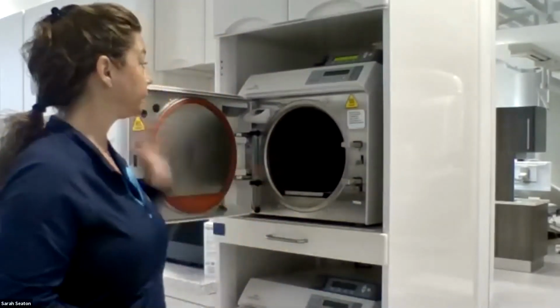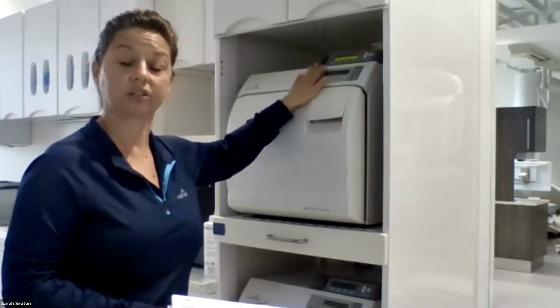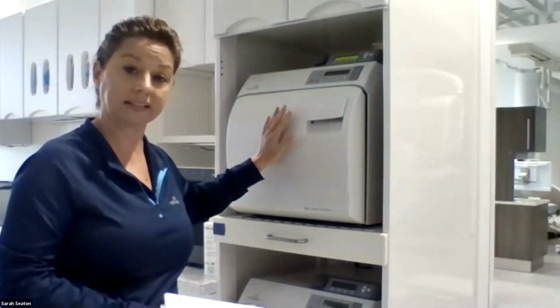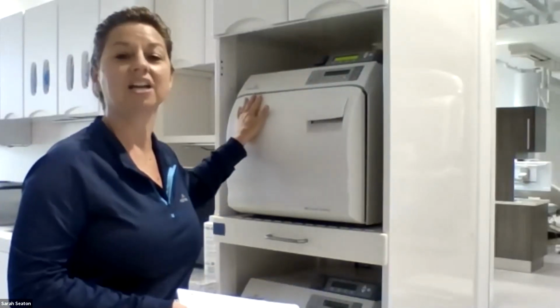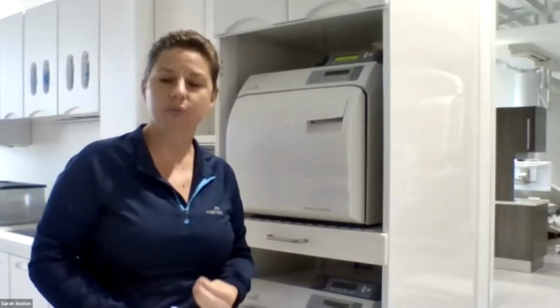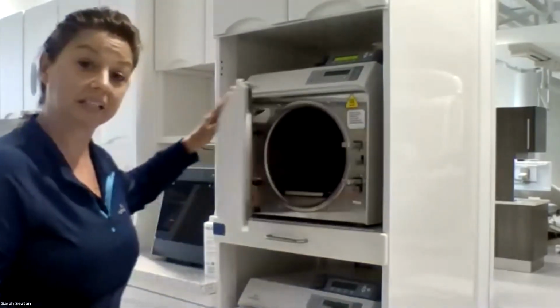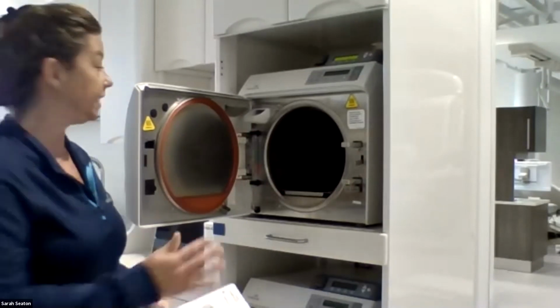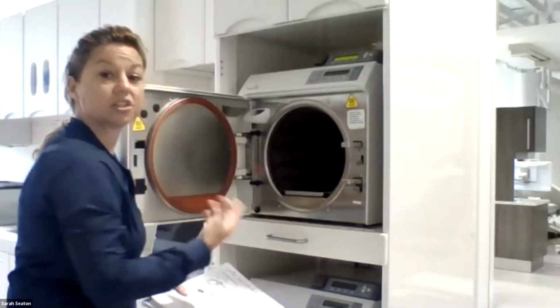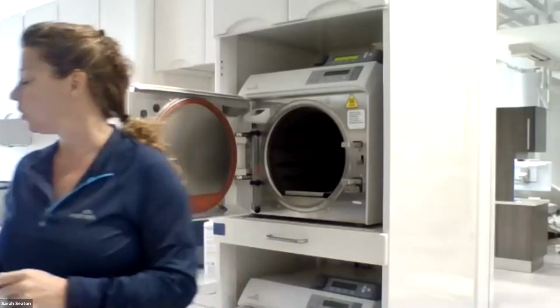But on a daily basis, it's important that you wipe down your sterilizer every day with a disinfectant. Now, you do want to keep in mind that it needs to be a quaternary cleaner to clean your surfaces externally. You do want to make sure that the unit is cool whenever you do your daily maintenance, because there are some internal surfaces that you will want to wipe down, namely your door gasket and its mating surfaces, so that it has a nice good seal, okay? The only other thing that I would suggest for that daily maintenance is if you use a surgical milk or a rust inhibitor on your instruments, it's important to drain your reservoir on a daily basis. And I'll walk through that process during the weekly maintenance, which is a little bit more in depth.